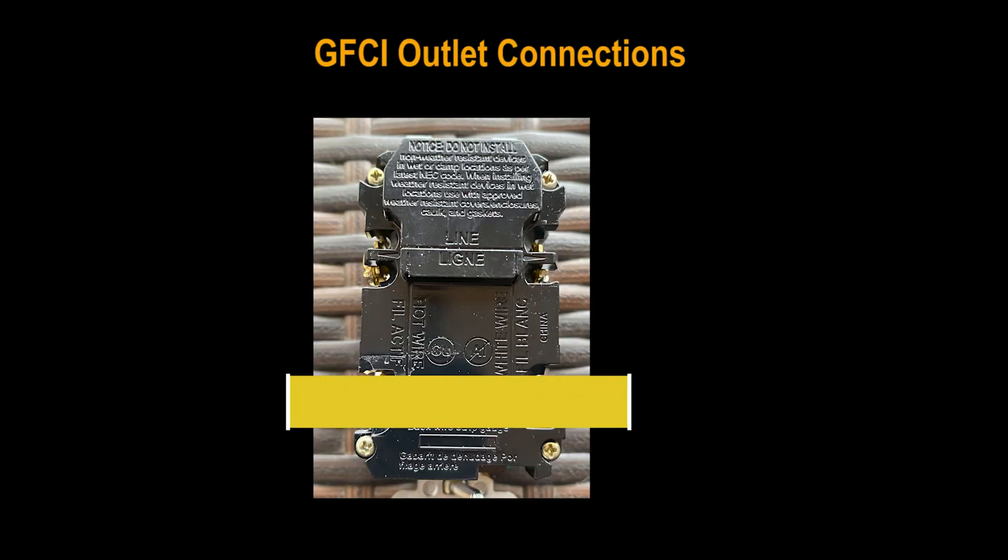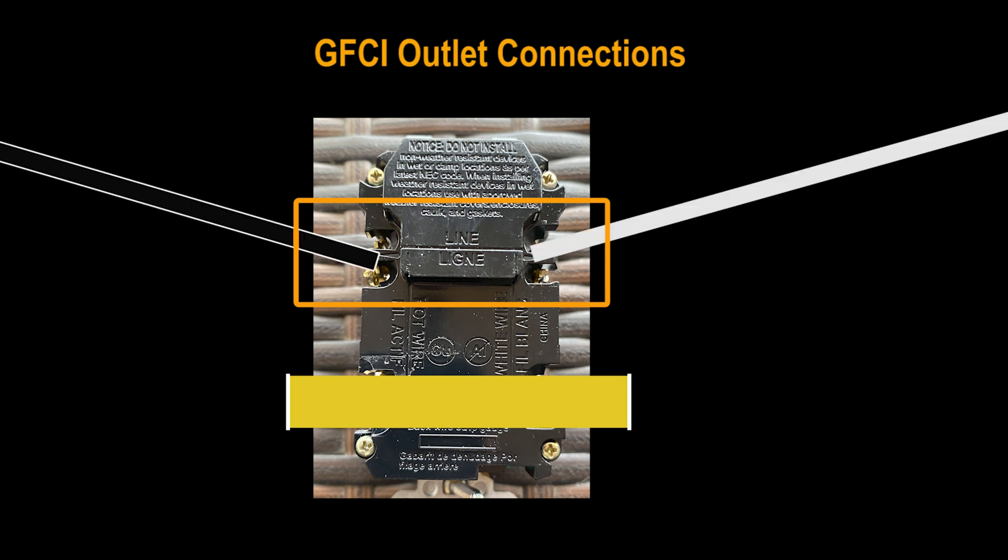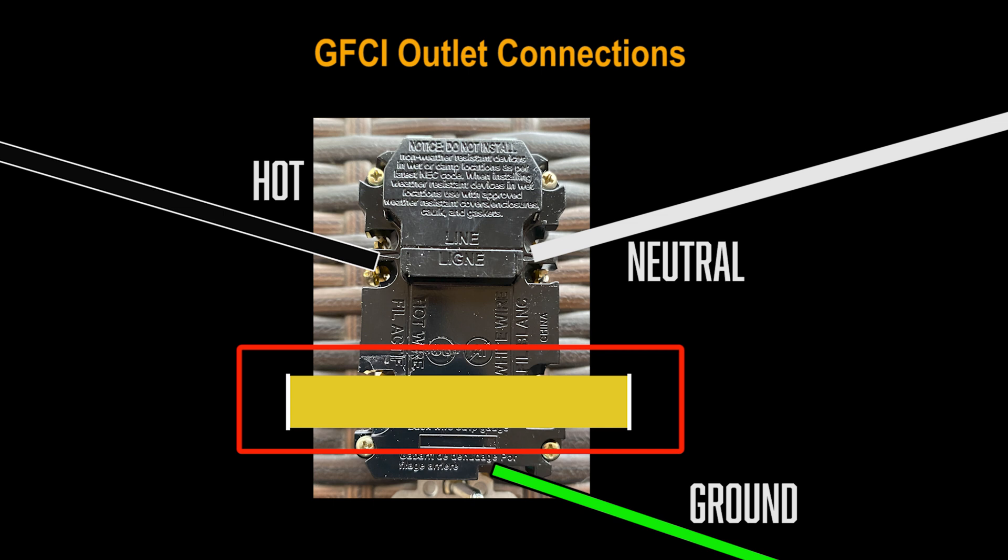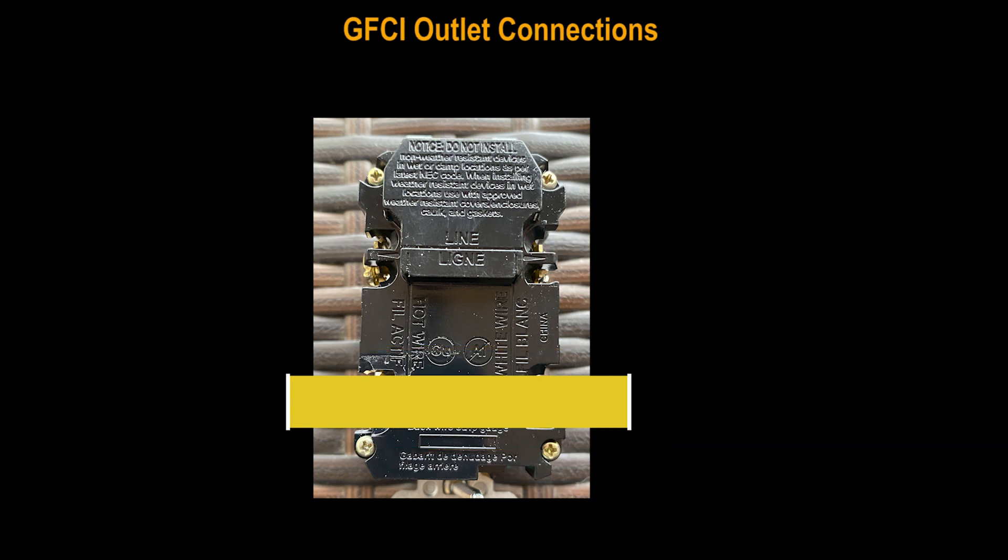On the back of GFCI outlets, there is a main line connection, which we have gone over earlier, which connects the hot and the neutral wire, which feeds the power to the outlet is connected to. Plus it adds a second set of terminals which are covered with the tape on a newly purchased switch. The covering tape is there so it can be wired as a basic outlet at first before connecting any optional lines. So just the three contacts are exposed at this point: the hot, neutral, and ground. The sticker also stops you from mistakenly connecting the hot or neutral into the wrong slots, which can still bring power but will not let the GFCI protection work properly.